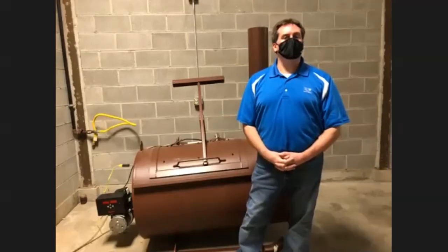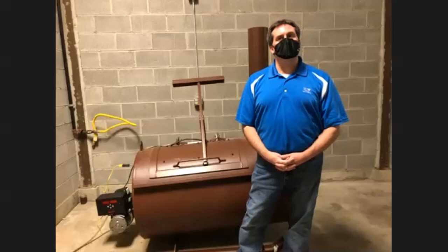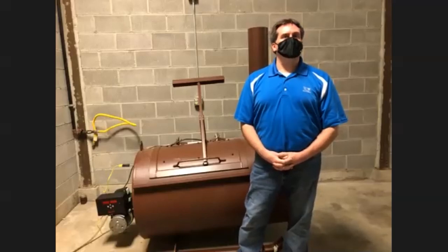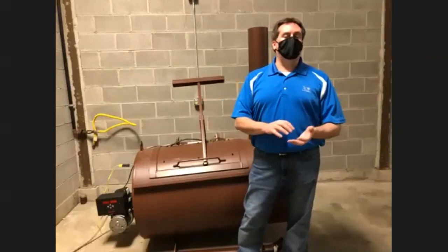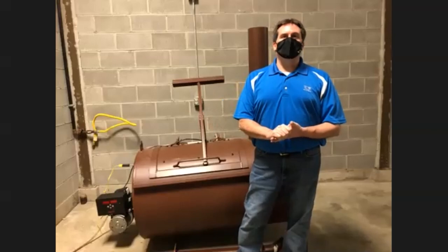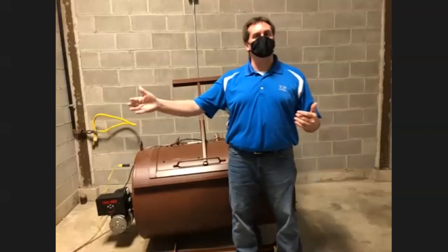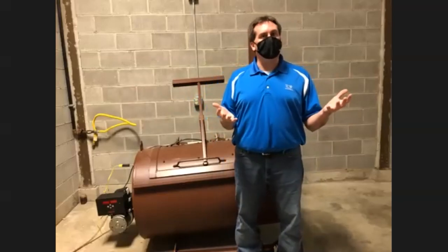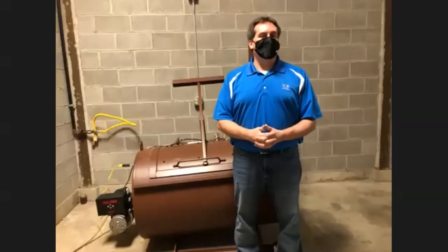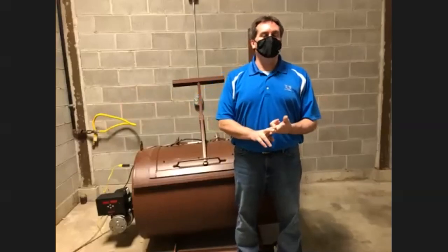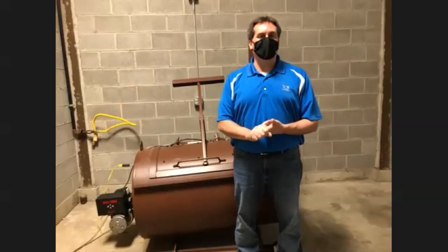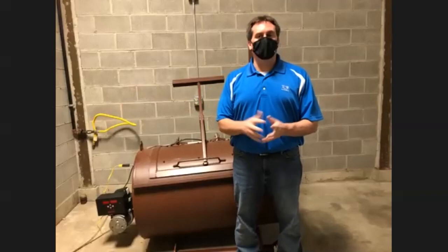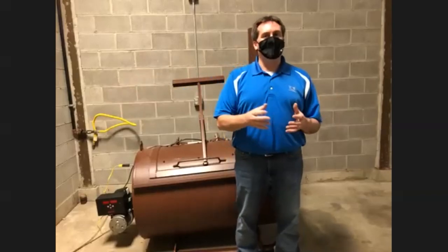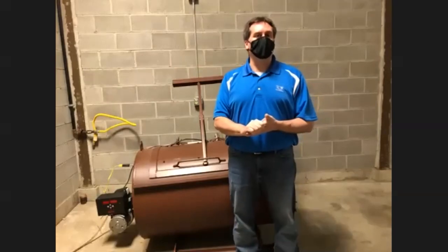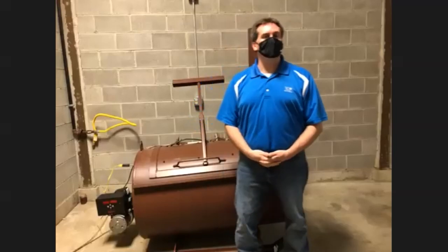What size wire should we have for the wiring for the outlet for that? That depends on how far away you are, and the electrical codes you have to follow. You need to carry 20 amps, whatever distance you need to be. Chances are, I'm going to say probably 12 gauge, probably nothing wider than that, but it depends on how far a distance you're going as well. Do not hook it up to an extension cord, because you'll have a little voltage drop through those. You just need to verify your distance from your power supply to your cremator, check the proper code, and what's necessary to carry the proper voltage in that distance, what gauge wire you may need.